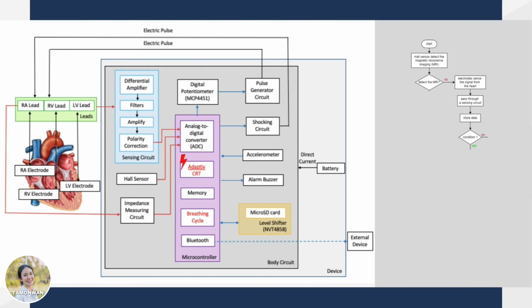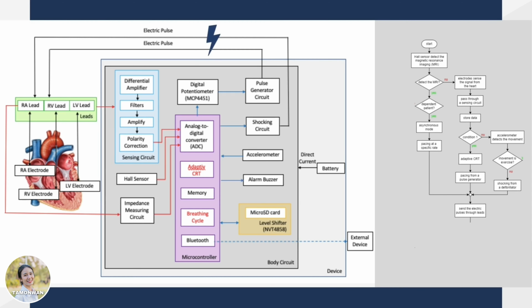After that, there is the condition to separate the patient that they should be pacing or shocking. For pacing, the signal passed through the adaptive CRT algorithm that we will explain more in the next part. Then send it to the pulse generator to generate the electric pulse. And for shocking, the accelerometer will check if the fast heart rate occurs because of the exercise or not. If it is from the exercise, the device will not do anything. But if not, the signal goes to the defibrillator to generate the electric shock. Then the device sends the electric signal through the leads and stimulates each chamber of the heart with the electrodes.